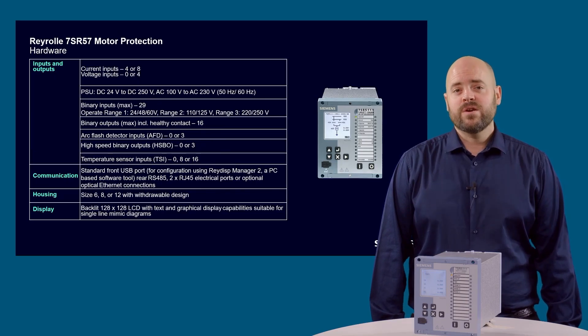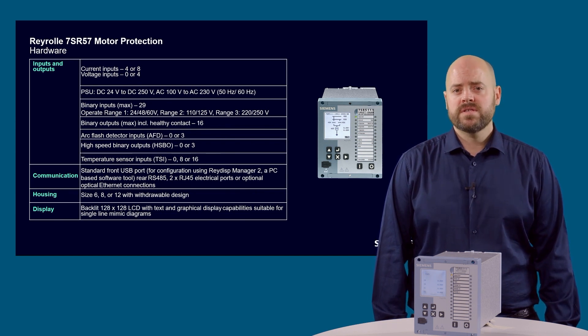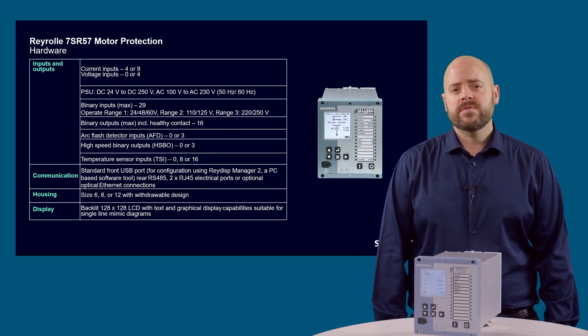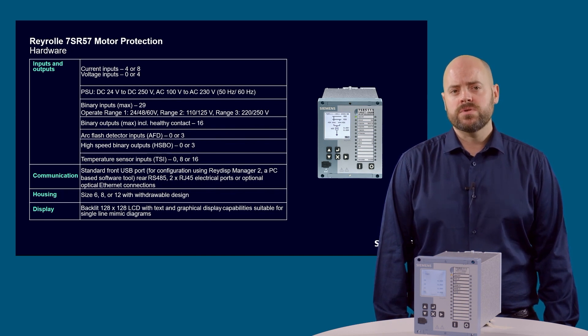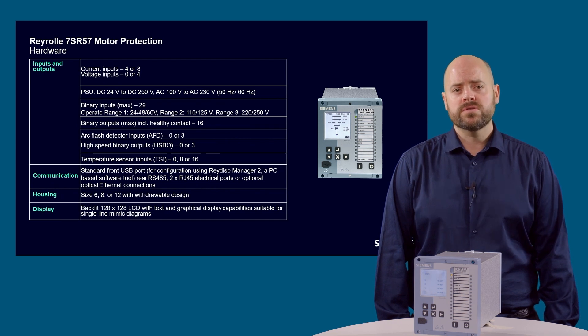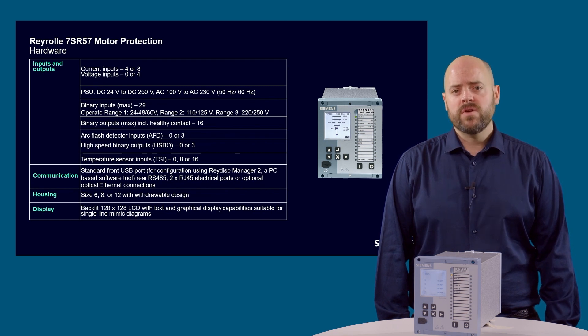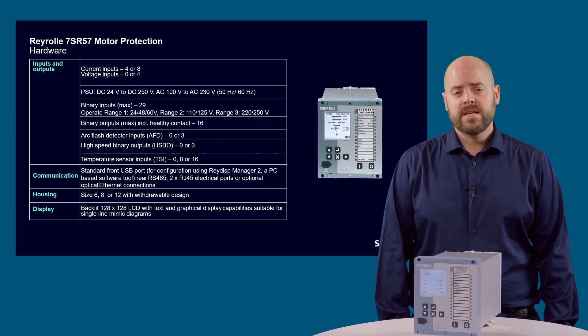Now let's take a closer look at the hardware. 7SR5710 motor devices have 4 CT inputs, and 7SR5711 and 7SR5721 motor devices have 4 or 8 CT inputs and 4 VT inputs. A single power supply covering all substation auxiliary voltage supply levels is used — no separate ordering options are necessary. The binary inputs have selectable operating levels and each binary input can be configured individually if required. There are optional arc flash detector inputs, high-speed binary outputs and temperature sensor inputs.